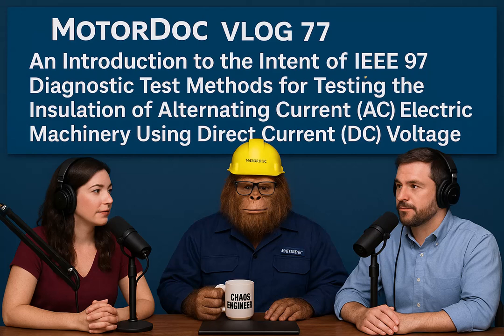Exactly. However, they do mention in some specific cases, say on a machine already in service where you suspect failure might happen soon anyway, you might choose to continue the test all the way to breakdown. Why would you do that? It could potentially help pinpoint the exact location of the fault and maybe give you an idea of the kind of damage it might cause if it failed while running, but that's a specific decision, not the norm.